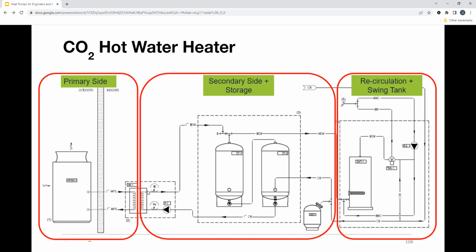Anyways, on the secondary side, you're bringing this hot water in and it's maintaining these storage tanks, right? Keeping it around 140, 150. And then you have your pumps to get the right pressure and the right flow to ensure you're getting the right temperatures for these tanks, right? So you have the city water going in at the bottom of the tank, and then you have your hot side of the tank over here, and it flows into these tanks accordingly. And then that hot water is sent out to the system, mixed with a mixing valve to get around 120 degrees, and then brought out to the space that way.